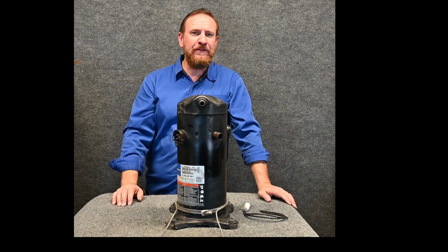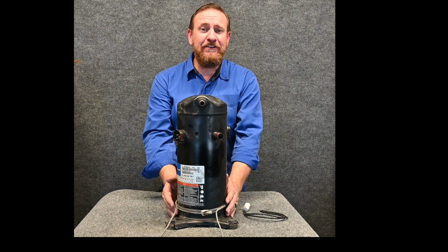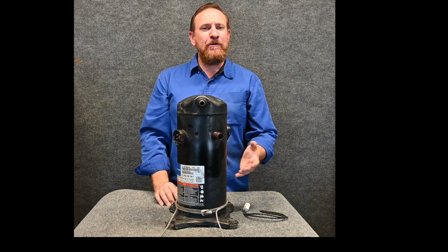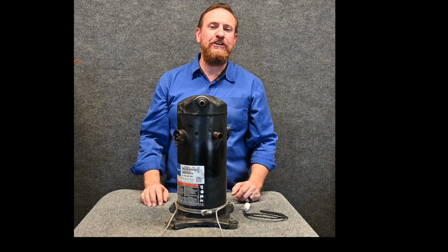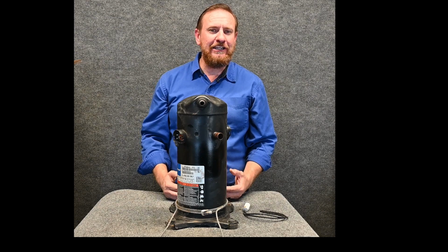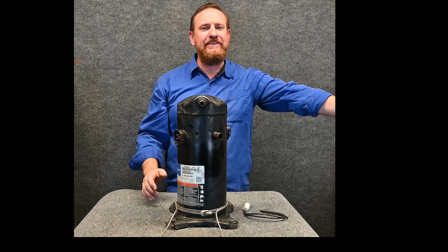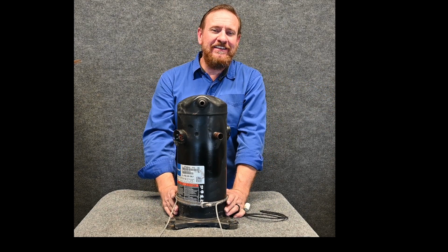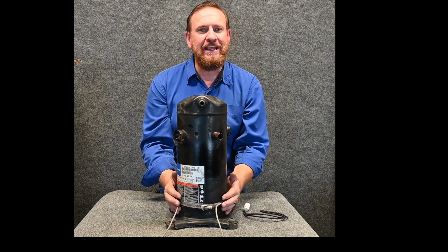this crankcase. Another important thing about crankcase heaters, most of the time we want to have it where a crankcase heater is only heating when the unit is off. When the unit's running, we don't need it. Remember, the reciprocating compressor had the discharge line run all the way into the bottom just for that purpose. So when the system is running, I don't need to spend money buying electricity to heat up this oil and then spend money taking the heat out of the oil at the condenser. So we typically want to see these wired to where when the system is off, the crankcase heater is on. When the compressor is running, the crankcase heater is off.